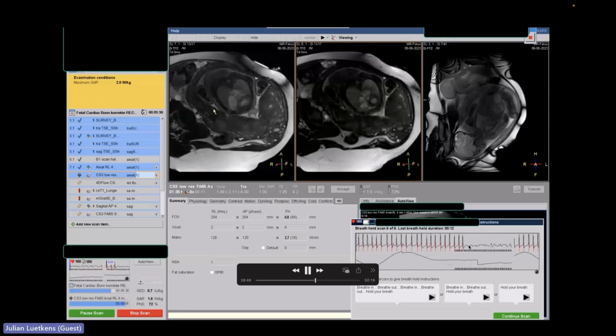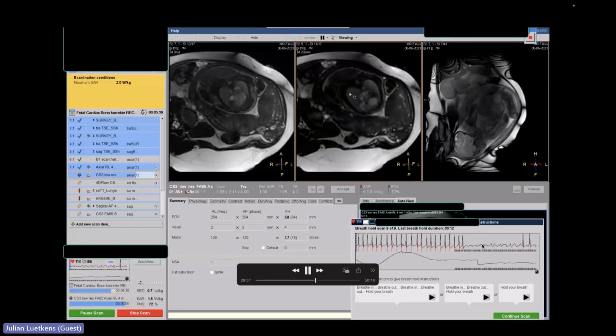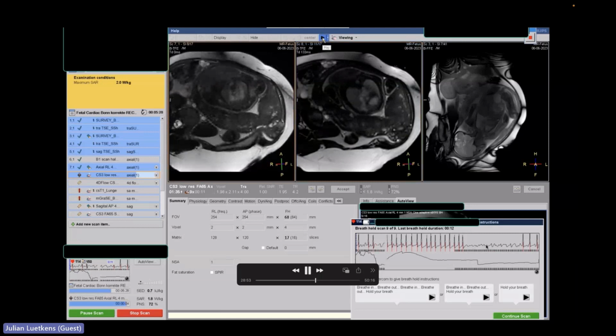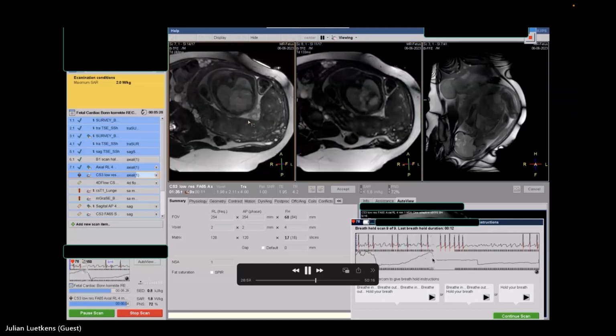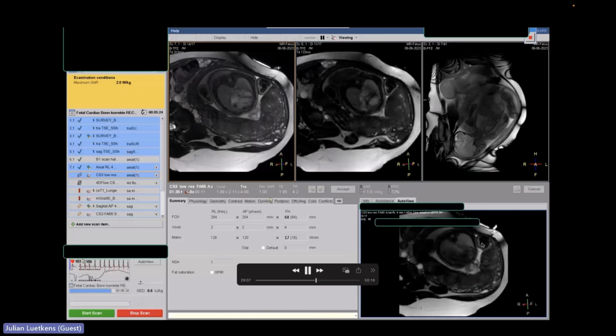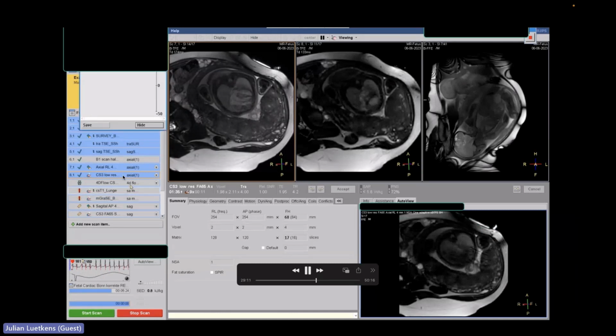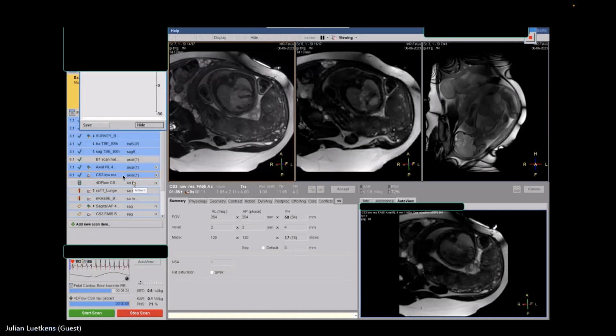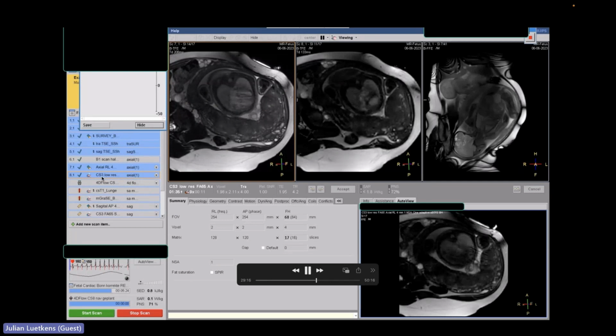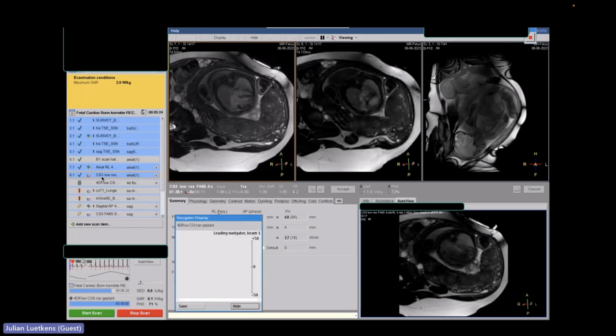Okay. What you can see over here is that now we have a loss of a trigger signal, maybe due to fetal movement. And the scanner is scanning all the time. There are some trigger points left, and the sequence doesn't abort. This is good. And we didn't repeat it because it was the last slice. And now the 4D flow sequence starts.